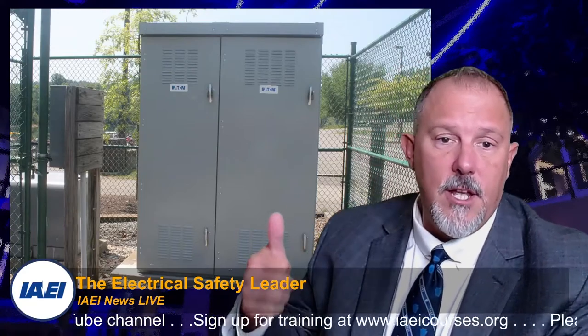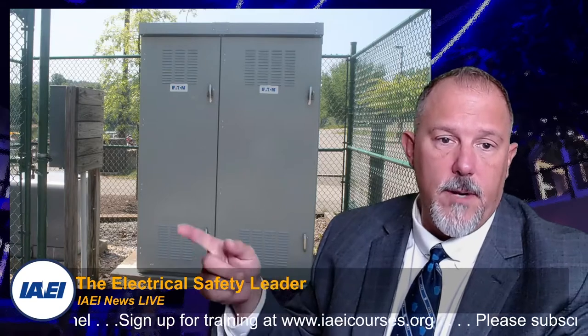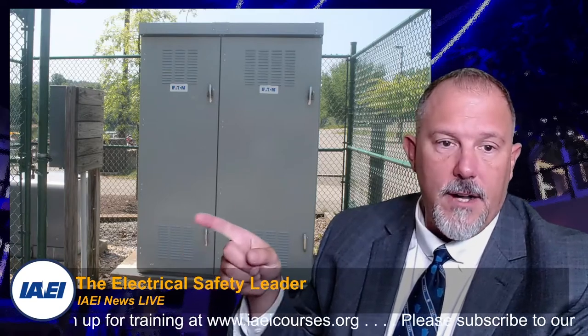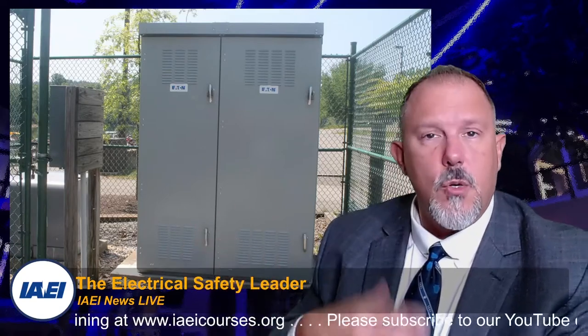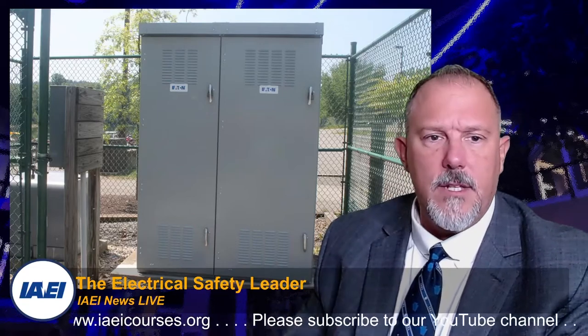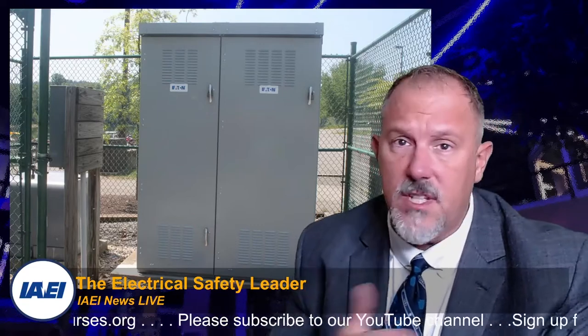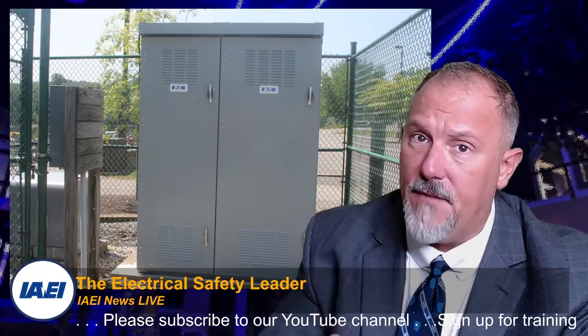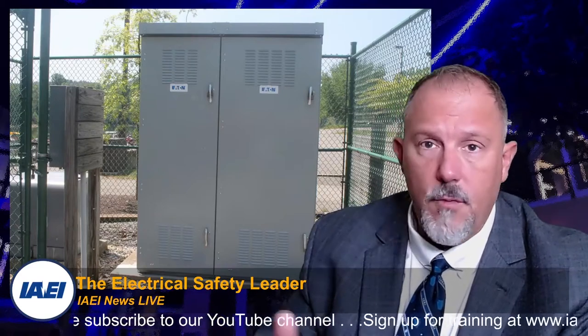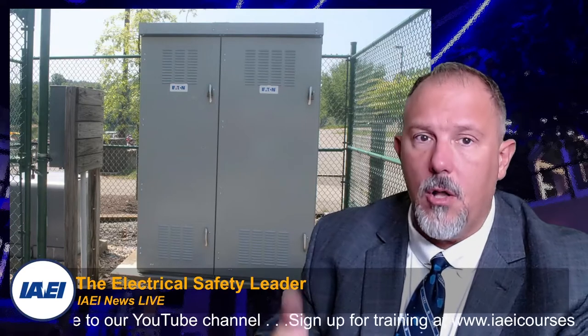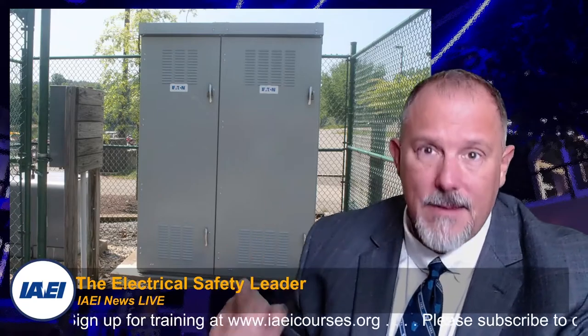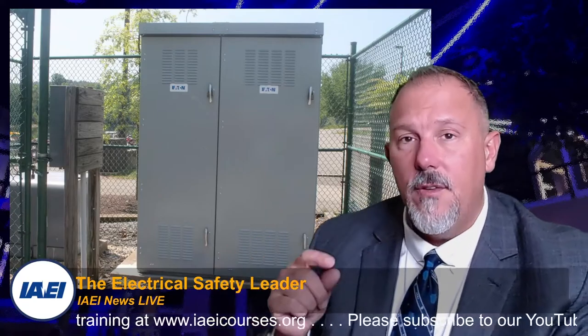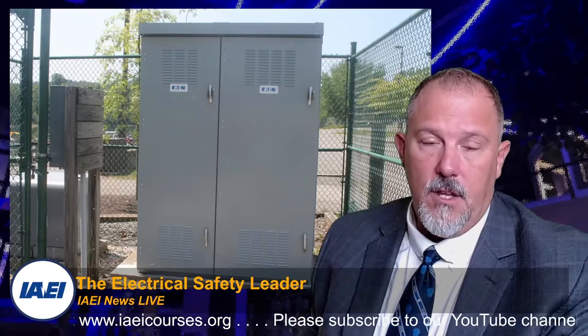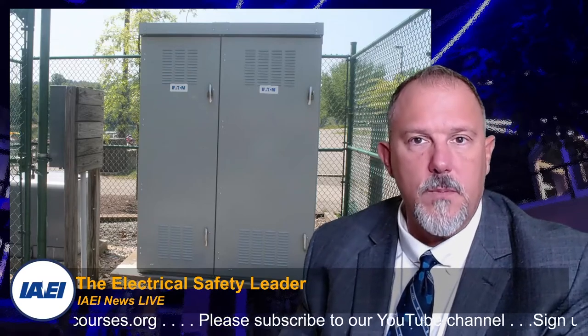You'll notice in this, you have this nice big gray box, but look over here, you've got the transformer — short circuit current ratings, interrupting ratings, the proper chapters 1-4 still apply, even though you're in Article 555. Chapters 1-4 apply generally; you've got to follow all of the rules. The available fault current at this panel is going to be pretty significant, especially because you're right at the secondary of that transformer with a very short run of conductor.